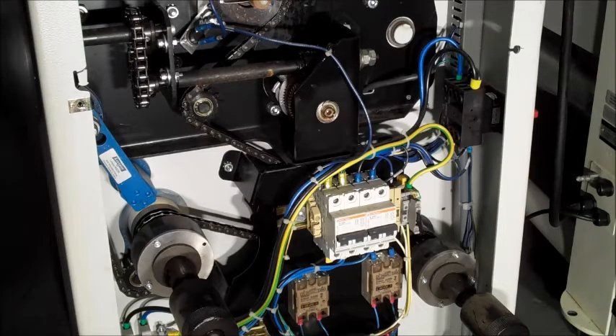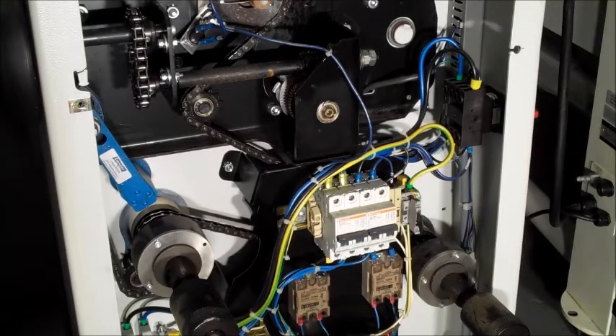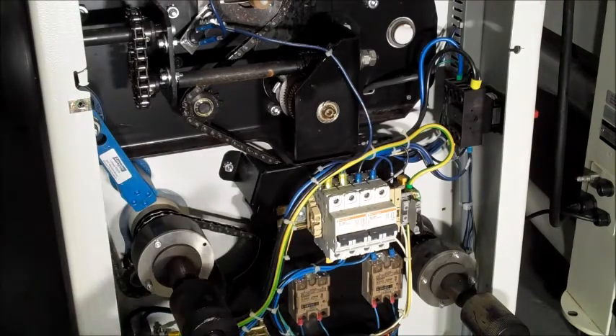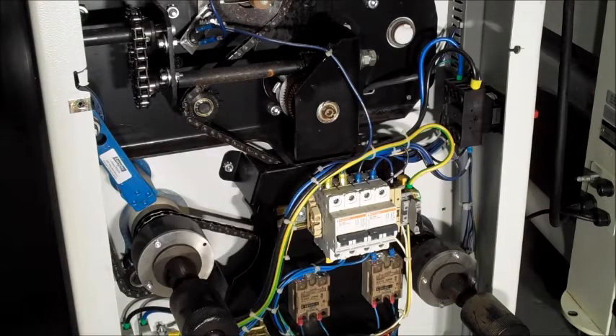So if you take a close look at all of your line voltage wires, you may find a burnt one or shorted one. It is rare, but from time to time we do have problems with the actual line voltage coming into the machine. So if you're getting some strange results, you may want to take a close look at the power that's coming in. Not a common problem, but it has happened.